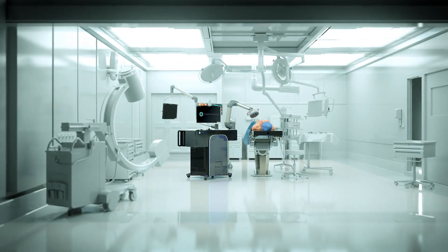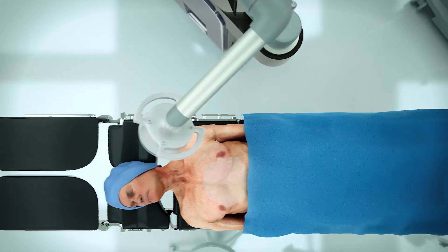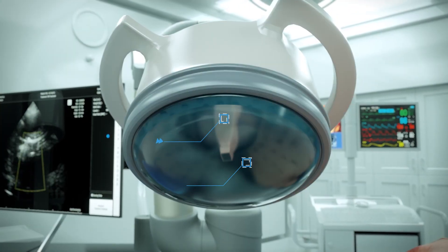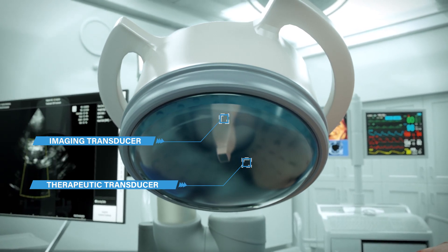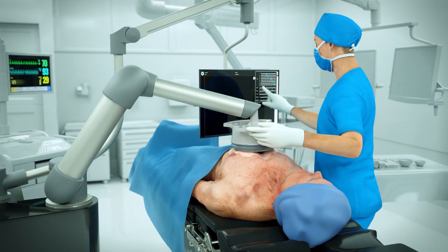Cardiowave's ValvoSoft platform is currently under clinical investigation for a restricted group of patients. At the heart of the platform is the applicator, which contains both an imaging ultrasound transducer and an independent therapeutic transducer, which can precisely focus the ultrasound in the target zones selected by the cardiologist thanks to real-time electronic steering.